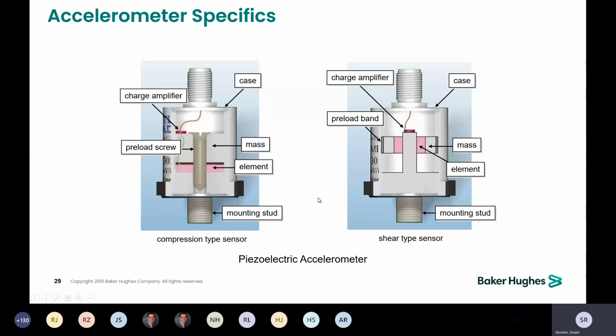To get around that, more recently they have come out with the shear type sensor, which uses a piezoelectric element with a reference mass out on the end, and there is no preload bolt. This is hung out in free space, and as that reference mass moves up and down due to inertia, it flexes this piezoelectric core, and we read that current from that core. Not having a stack of items makes it much less thermally sensitive. So these we see going out to 900 degrees F or so, where generally the compression types are limited to 350 to 400 degrees F.